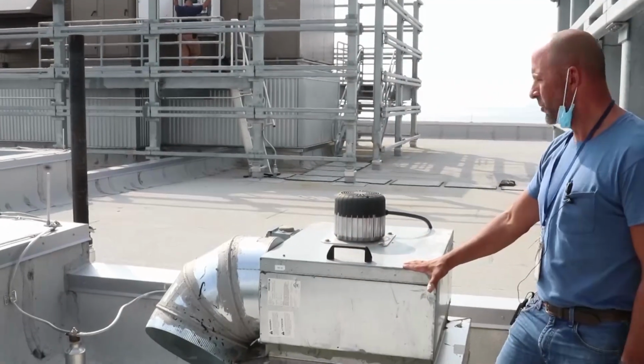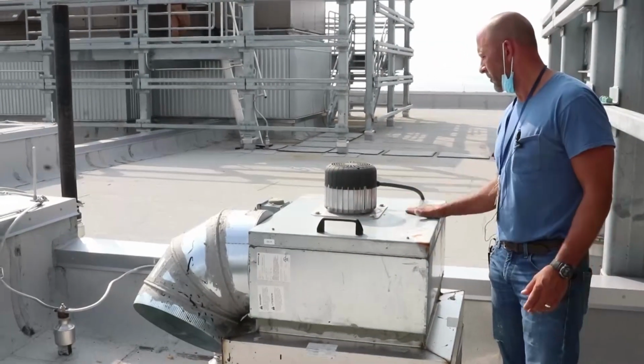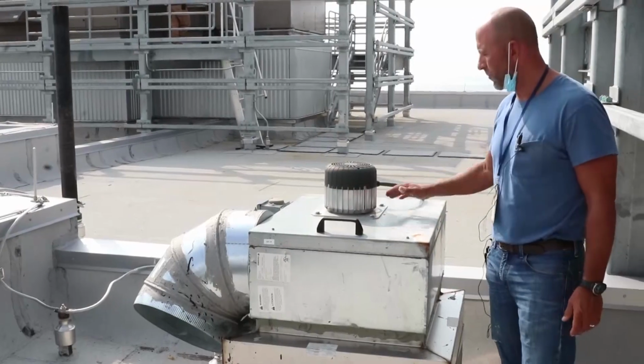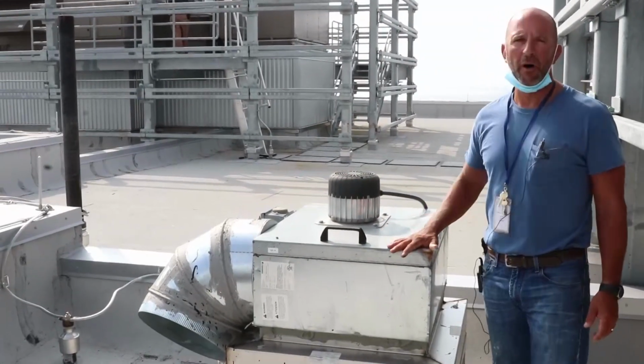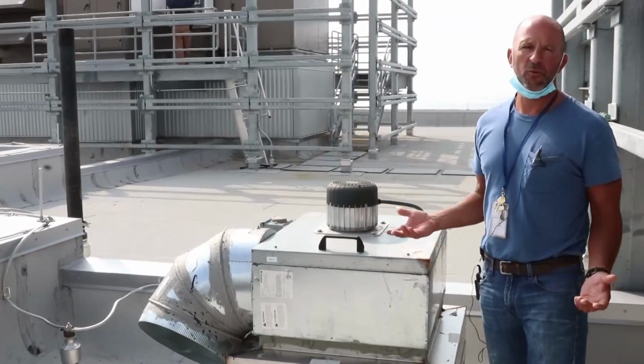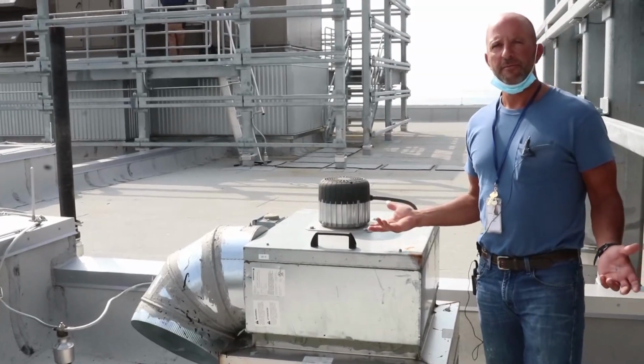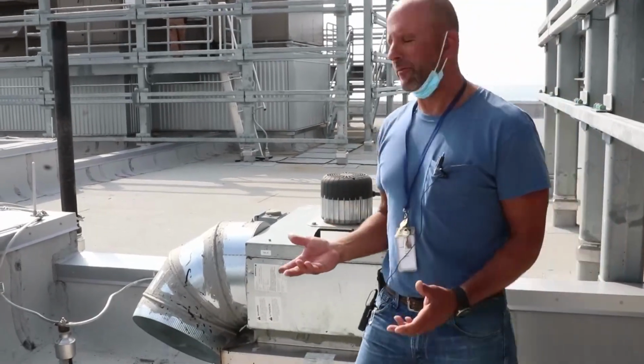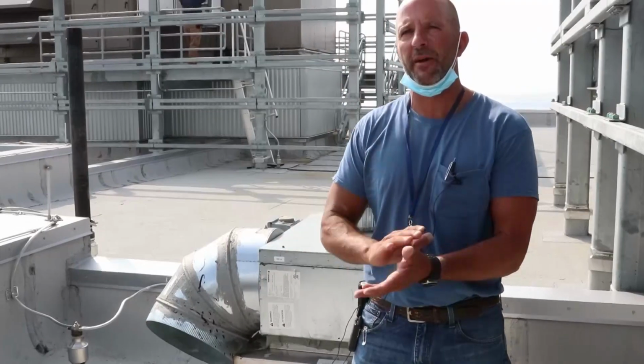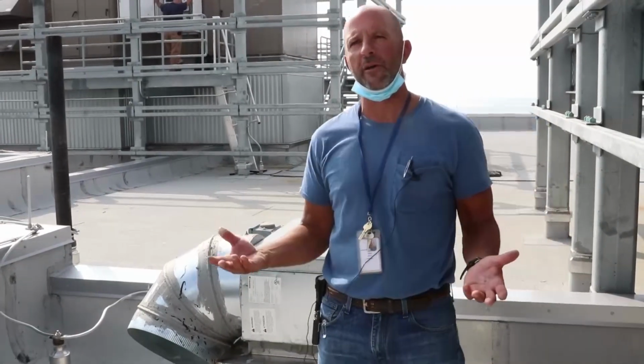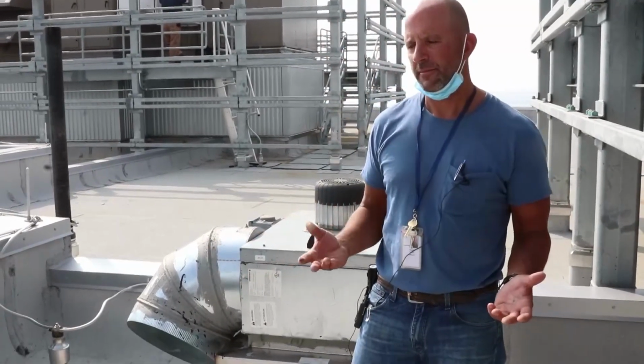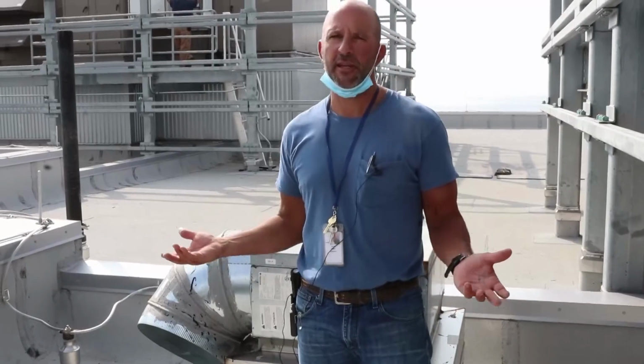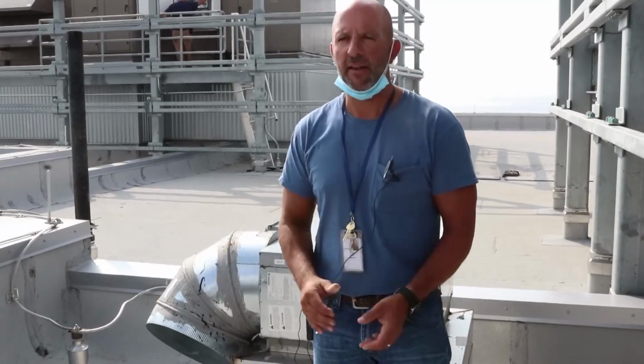Really not much you have to do with these. There's no greasing or oiling of these motors, they are sealed. You'd want to open them up every once in a while, shut them off, and look at the wheel to make sure there's no lint on it. You wouldn't really get to that point, but you want to make sure the wheel's clean, it's an aluminum wheel, so you're getting the performance out of the fan.